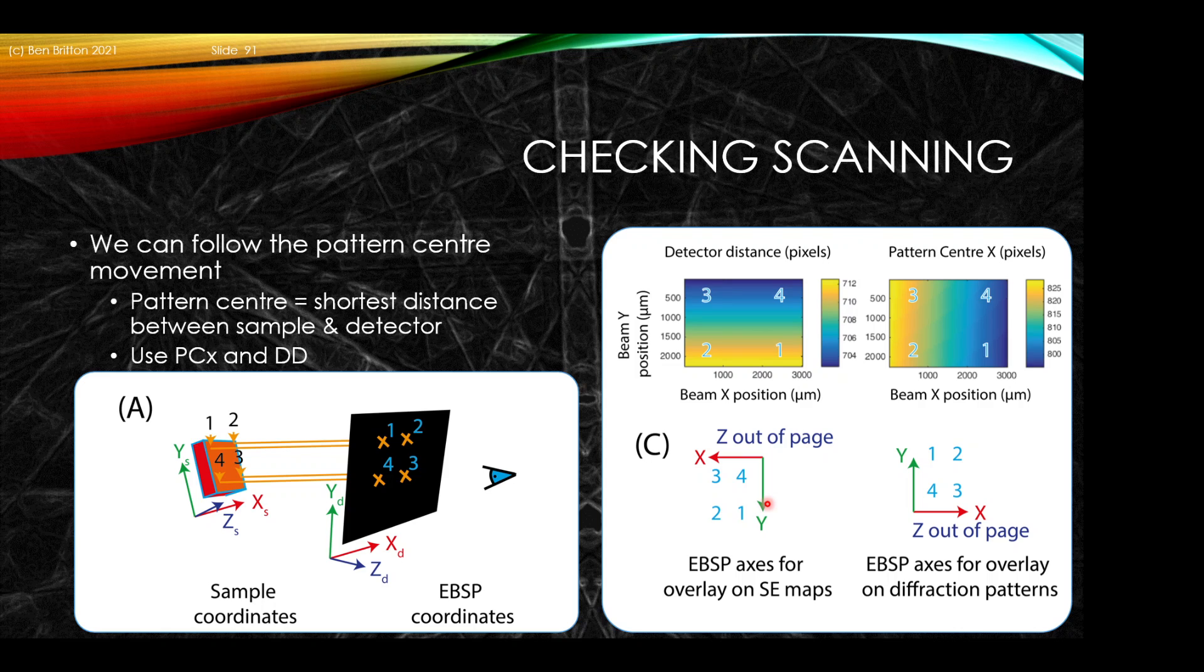So that shows we have Y pointing up the sample. If we look at the X convention as we move across this detector, this is the short X, this is the longer X. The pattern is moving from short to long. So we see the X is pointing on our sample on top of the SEM from right to left, and Z is pointing out of the plane of the page. Some may ask why we have not used PCY. There is an ambiguity between different software families, whether you count from the top or bottom of the diffraction pattern. That's why we've used the detector distance instead.